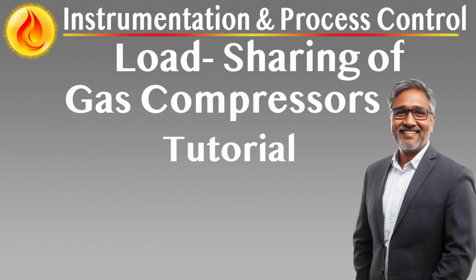Recycle balancing. When recycling becomes unavoidable, compressors moving away from surge close recycle valves in a staggered fashion. Compressors moving toward surge keep their recycle valves open while others catch up. This ensures uniform valve behavior and extends machinery life by avoiding overuse of any one unit.